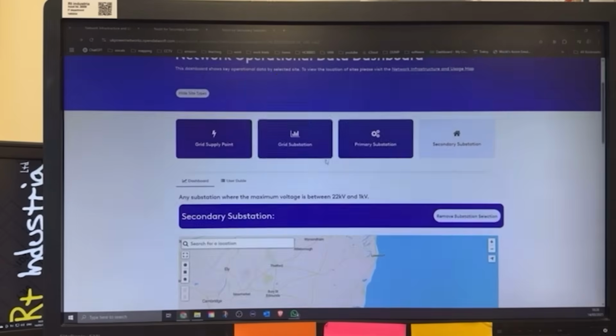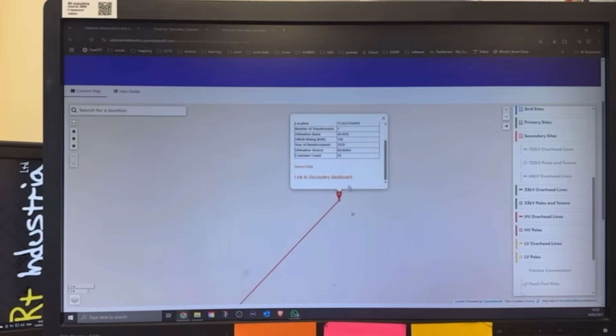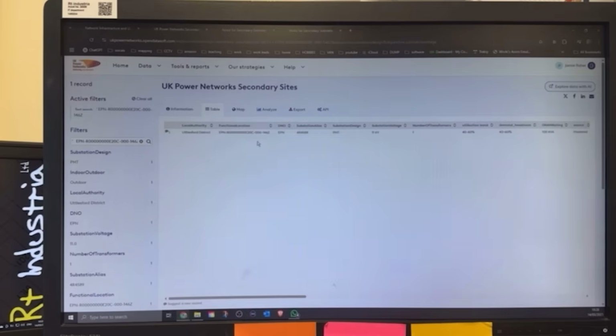So it would have been hard to look at this open infrastructure and find out what was going on otherwise, but the source data is also there - it tells you the district, the EPN, number of customers, 11 kV, transformers, 46% utilisation, but it is a 100 kVA transformer so it should be able to handle it - it should be able to handle that 17 kilowatts.